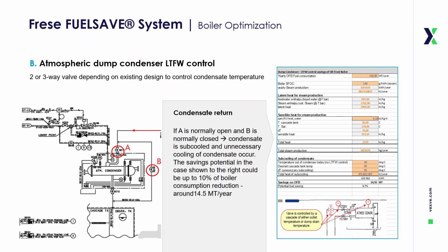The impact of this optimization is significant. Avoiding subcooling reduces boiler fuel consumption by approximately 10%, which typically translates into an annual saving of around 14.5 metric tons of fuel for the vessel in the case example showcased. To achieve this, the Frese FUELSAVE system integrates the atmospheric dump condenser with either a two-way or three-way valve, depending on the existing LTFW design. This precise control of condensate temperature not only improves fuel efficiency, but also enhances the overall thermal balance and reliability of the boiler system.